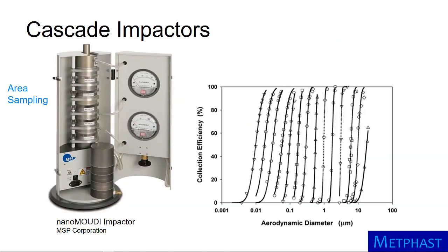Cascade impactors provide a way to collect particles in different size ranges. They pull air through a series of impactor stages that collect smaller and smaller particles. An example pictured here is the nanoMOUDI, which has stages with 50% collection efficiencies that range from 10 nanometers to 18 micrometers in diameter. The large size and weight of many cascade impactors limits their use to area sampling.